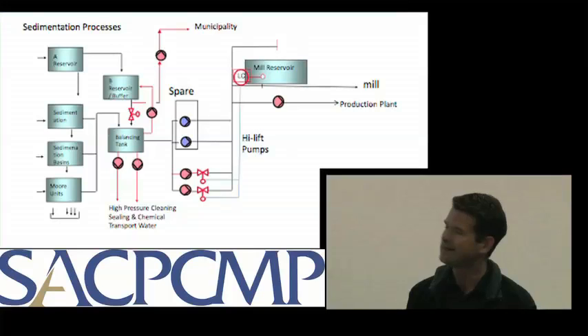This B reservoir was one of the key things, as I mentioned. Our idea was that if we switched the high lift pump station off and the river water was really dirty, we would continue to produce clean water into this B reservoir, or buffer level. The water coming from here would go into the balancing tank, and it's a bit counterintuitive, but we'd pump from that reservoir up to the B reservoir, and then once we came back online, draw more quickly off that and pump and catch up.